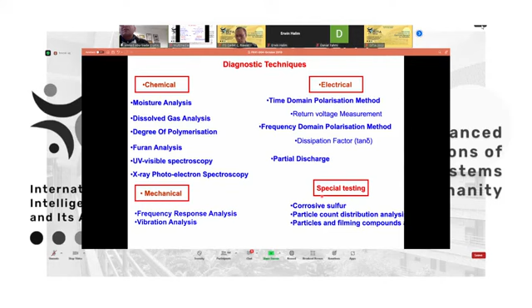So researchers and industry experts came up over the years with various diagnostic techniques, which can be categorized into chemical techniques, electrical methods, mechanical methods, and some special testing. Each of these techniques is responsible for finding the health condition of the transformer from certain aspects. For example, frequency response analysis is responsible for detecting any mechanical deformation in the core or in the winding. As you know, we don't have a window to look inside the transformer and see what's happening inside. So frequency response analysis is one of the techniques that can discover the mechanical integrity of the transformer externally.